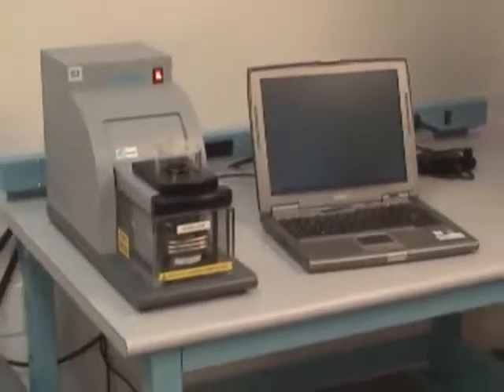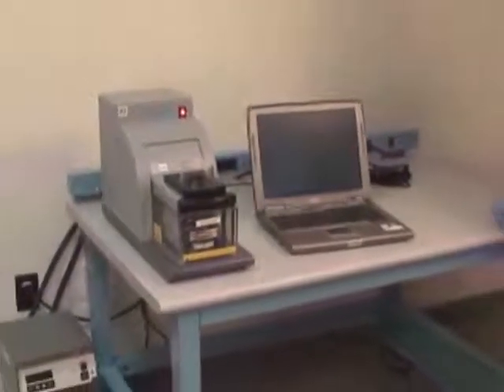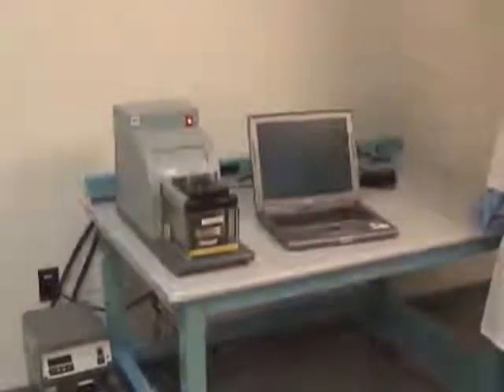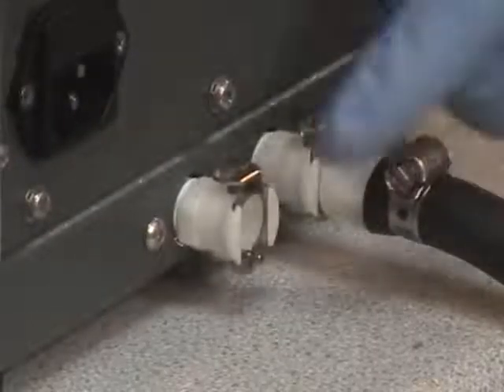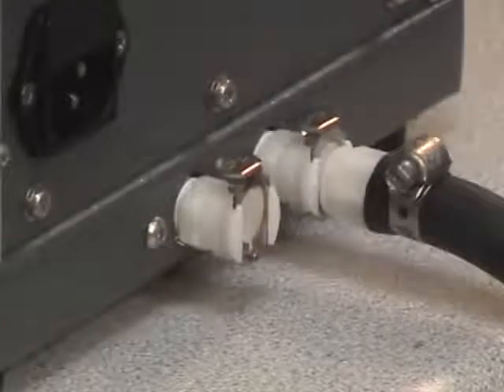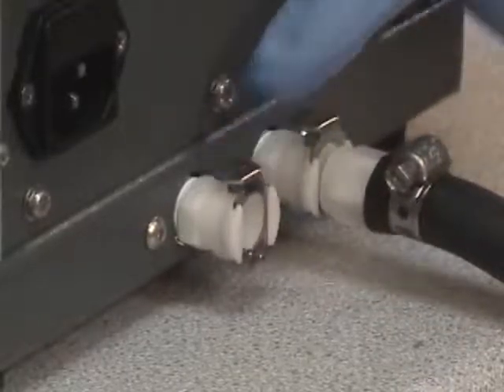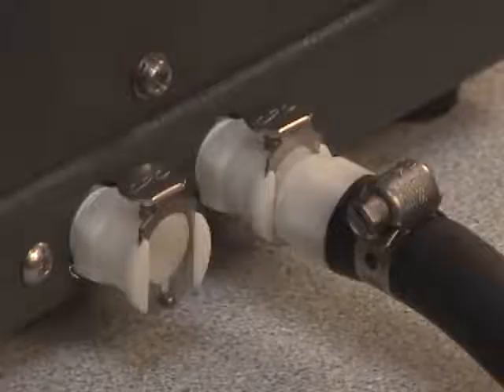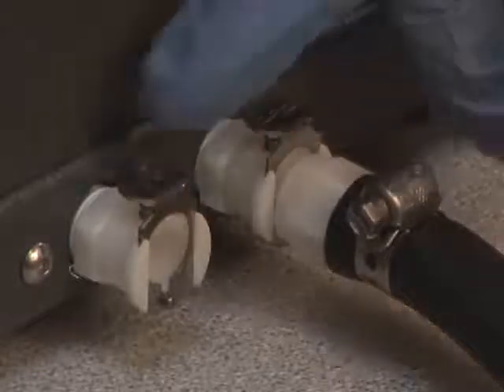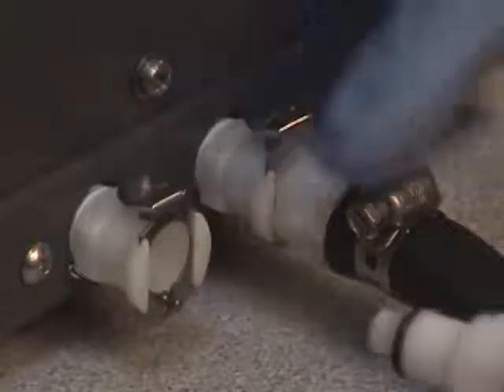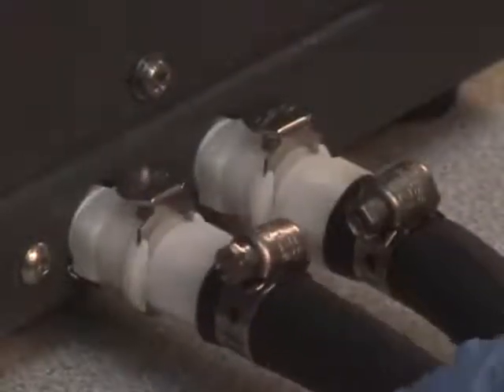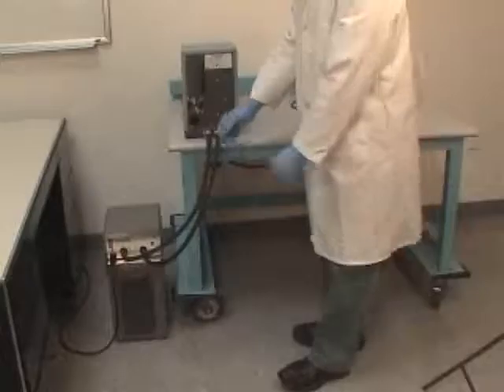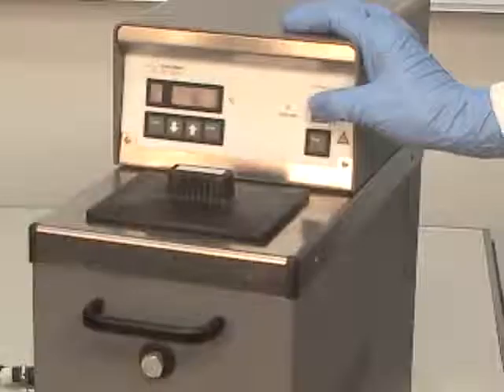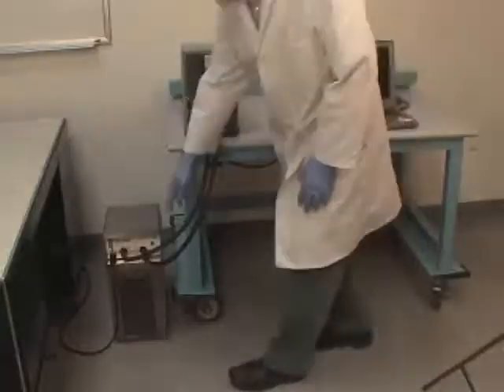Next, place the S2 instrument on a bench and attach the ends of the hoses with the quick connectors to the connectors at the rear of the instrument. Note that the hoses can go into either connector. However, make certain the metal release tab is in the down position. If the tab is up, the connector will not seat properly. The connector on the hoses should easily plug into the connector on the S2. You'll hear a click when the connection is properly made. Check that there are no kinks in the hoses, and then turn on the chiller and check for leaks.